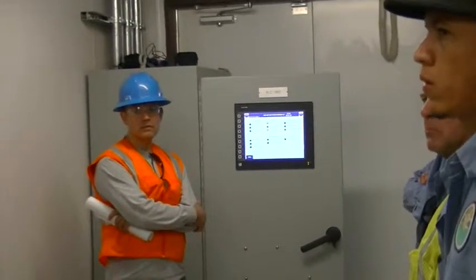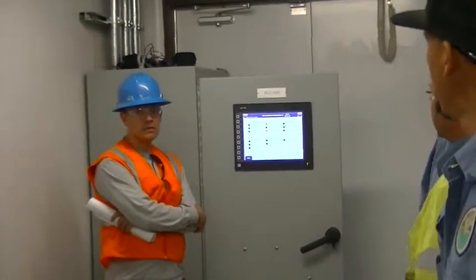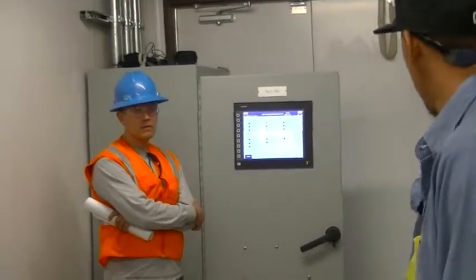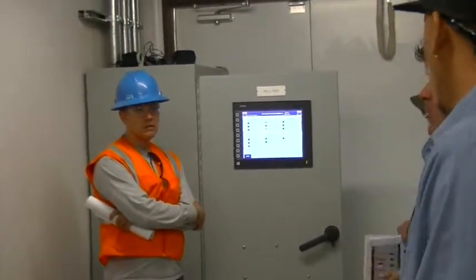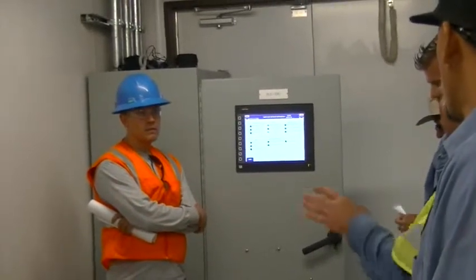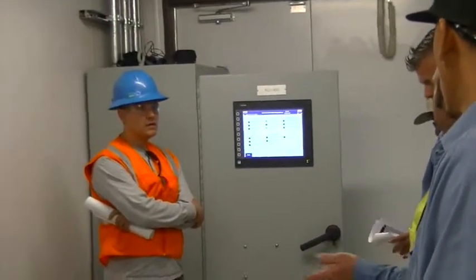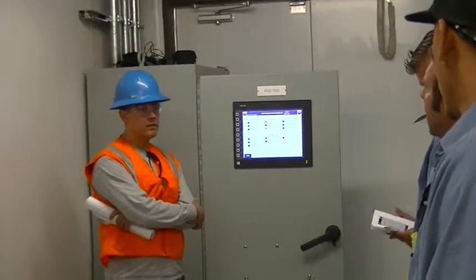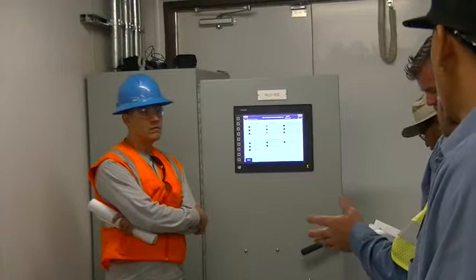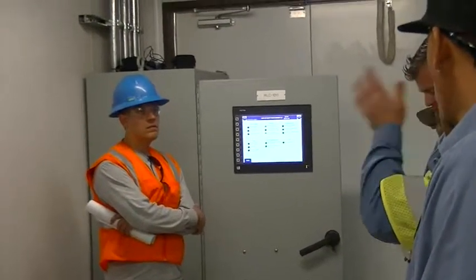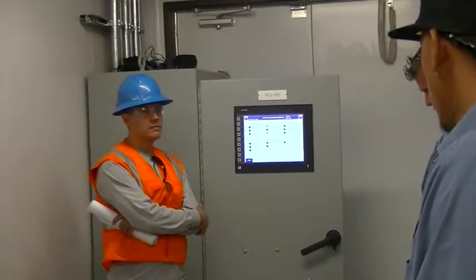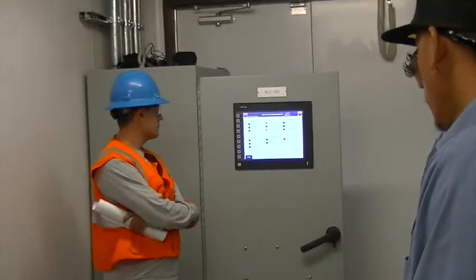And if it is running, it'll show up on that screen. Yeah, I know it'll show on this one, but I don't know if it'll show up back at the plant too. It would be good if it did. Generally, any of them we set up, we have them run at 8:30 on one of the days other than Friday, Monday, Tuesday, Wednesday, or Thursday. That way, if we go by a place and the generator's running at 8:30, we know it's called for it. That's probably what we'll do over here too.